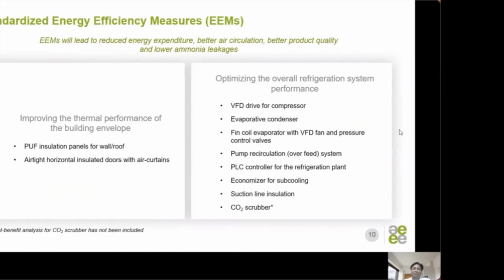For the refrigeration plant, we have recommended variable frequency drives for compressors and fans, evaporative condensers instead of atmospheric-based condensers, PLC controllers for the refrigeration plant, economizers for subcooling, suction line insulation, and CO2 scrubbers. Overall, the energy saving potential with these measures is around 20 to 25%.